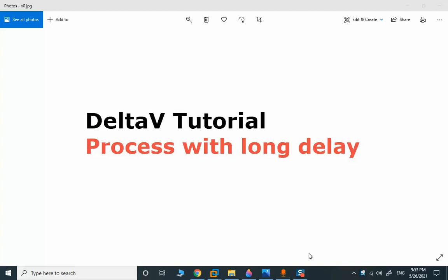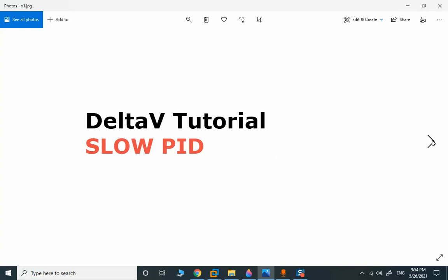This is the final part related to how to handle process models with a long dead time or long delay. We may encounter this type of process model rarely in industry, but we should have a strategy to solve the problem. When the delay or dead time of the process model is comparable to or greater than the time constant, we need to use special strategies to handle the control model.